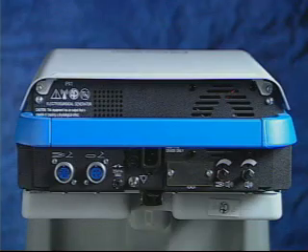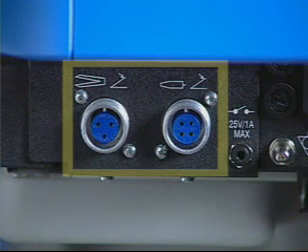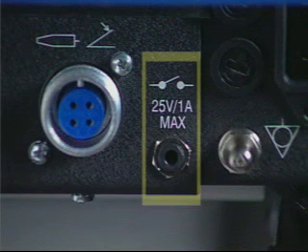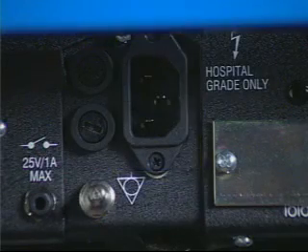The rear panel of the System 5000 contains the accessory jacks and volume adjustment controls. The first and second jacks are for connecting the bipolar and monopolar foot switches. Next is the smoke evacuation direct connector — a direct connection to the smoke evacuation system that synchronizes activation of the smoke evacuation unit to the activations of the electrosurgical pencil. Next are the power cord connection and the cover for the serial interface port.